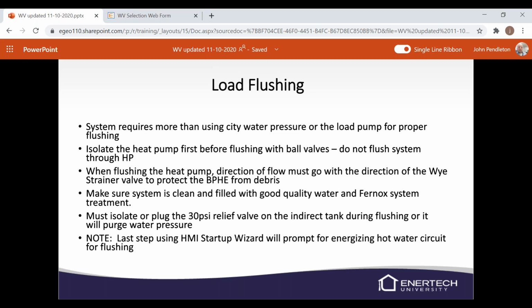Make sure you're always filling the system with clean, good quality water. And Fernox is a treatment. We need inhibitors in our antifreeze and water mixture. If we don't have those inhibitors, there are different materials in the piping, valves, and things like that, and it can actually start to break down those fittings. So we recommend an inhibitor. We use Fernox, and we actually have an Alpha 11, which is a Fernox antifreeze and inhibitor mixture that we sell. We sell the inhibitors, we sell cleaners, all from Fernox.